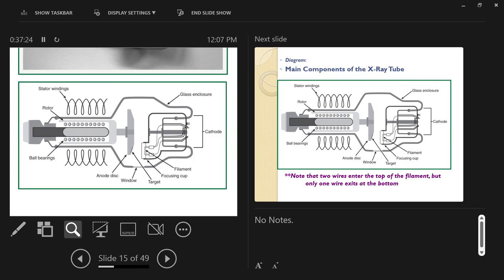The stator windings wrap around the anode shank. The rotor shank — the axle — is supported by ball bearings. The anode disc is made of dense tungsten metal, as is the rotor shank. The ball bearings are also dense metal, and since metal conducts heat, all of this heats up during exposures. The ball bearings heating up is primarily where x-ray tube failure occurs.